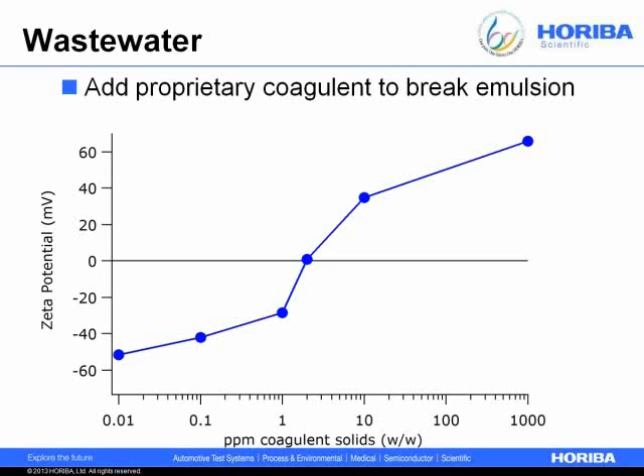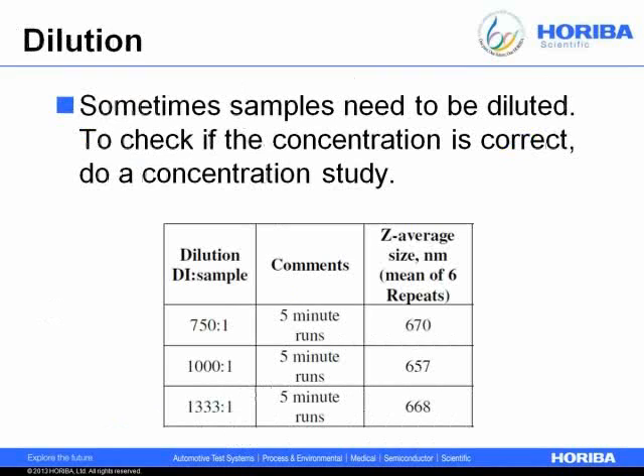Sometimes people want large zeta potential values (for stability) and sometimes small values (to break emulsions). Measuring the effect of additives on zeta potential is really the way this technique should be used. Regarding dilution: sometimes you need to dilute samples for particle size or zeta potential measurement. If you pay attention to continuous phase ions, that's usually not a problem. A concentration study confirms that measured size doesn't change significantly with concentration — across three concentrations the size barely varies, so you take the average and move on.